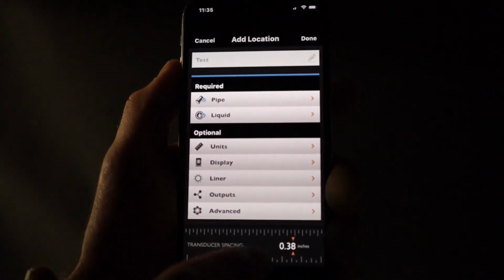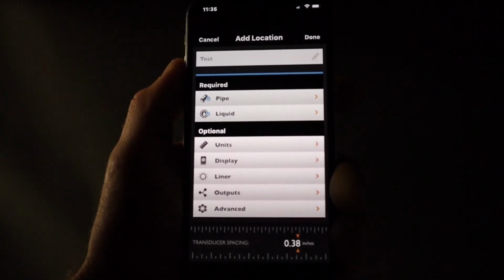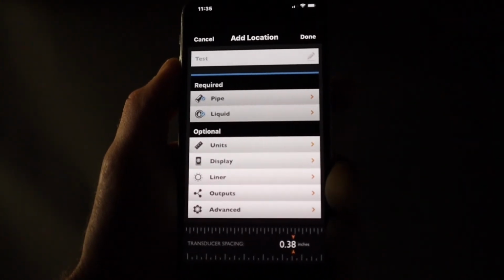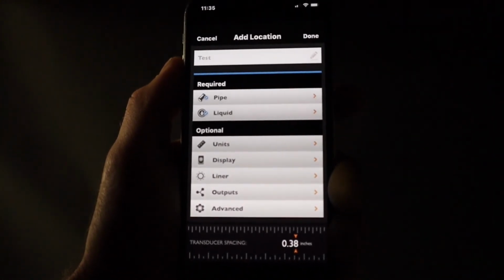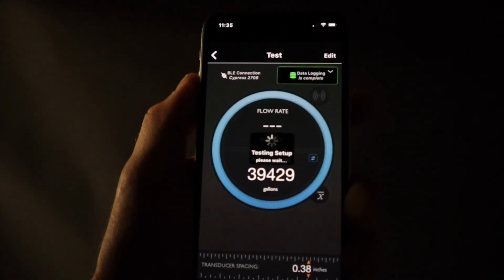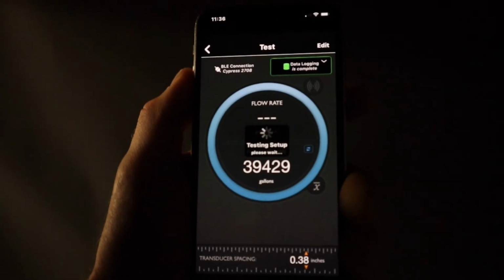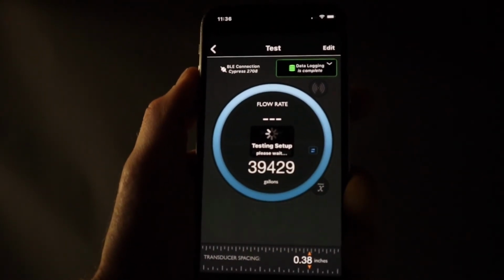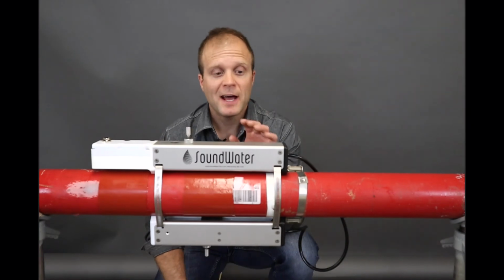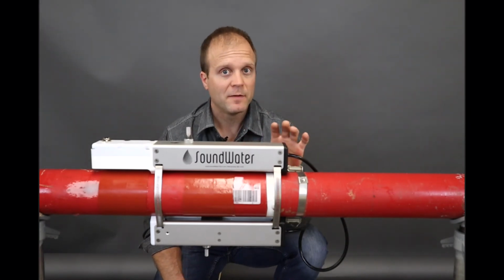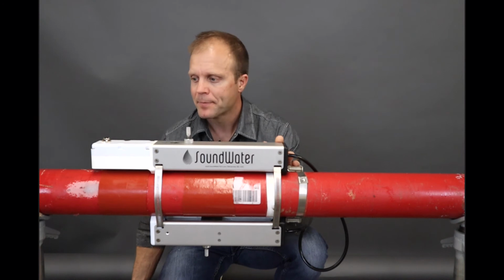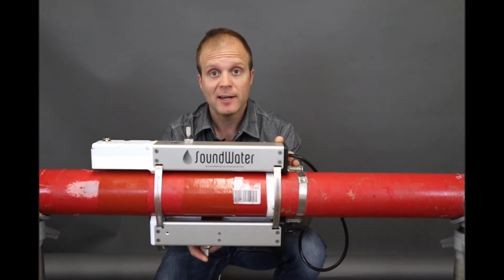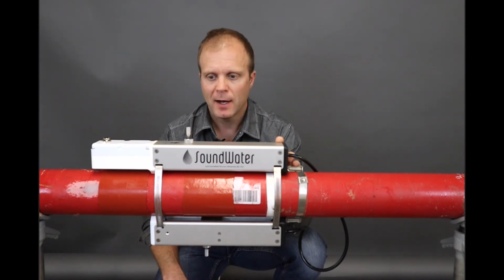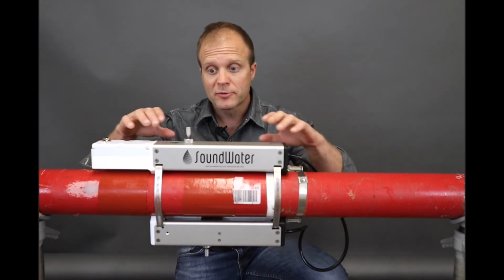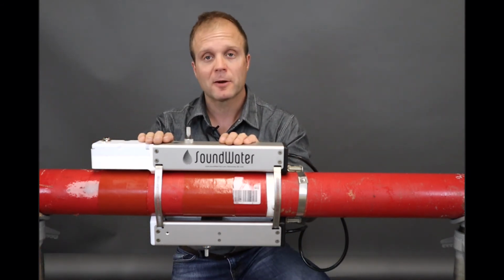And now at the bottom of the screen is the transducer spacing, which we'll use to set up and space the transducer on our pipe. So we can hit done here, and that configuration is now being sent to the flow meter, and the flow meter will try to measure flow at this point. So now that we have our transducer spacing that we got from our mobile app, we need to actually set it on the flow meter. So we have to access the movable transducer. So one side, the top here, this transducer is fixed.